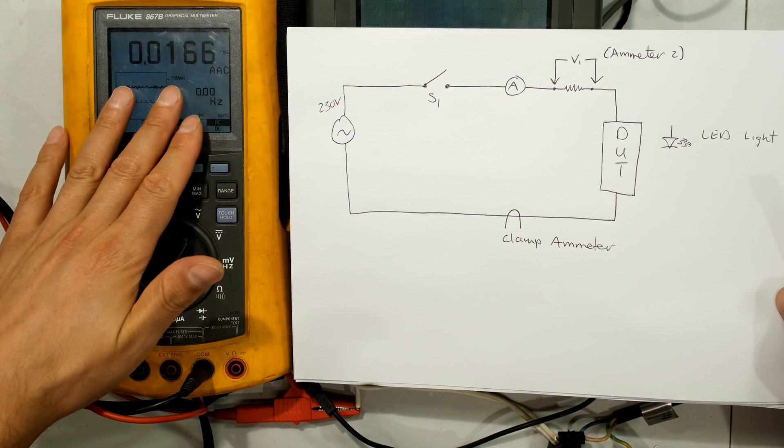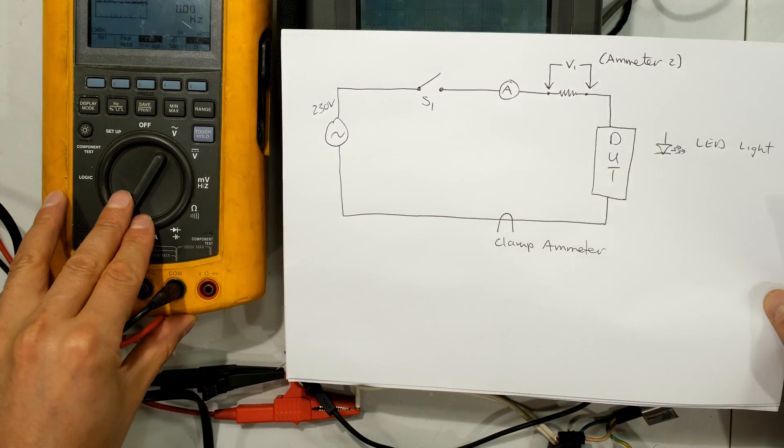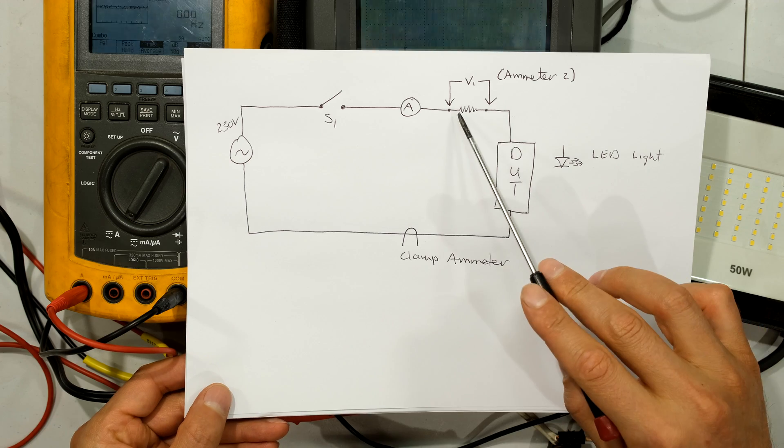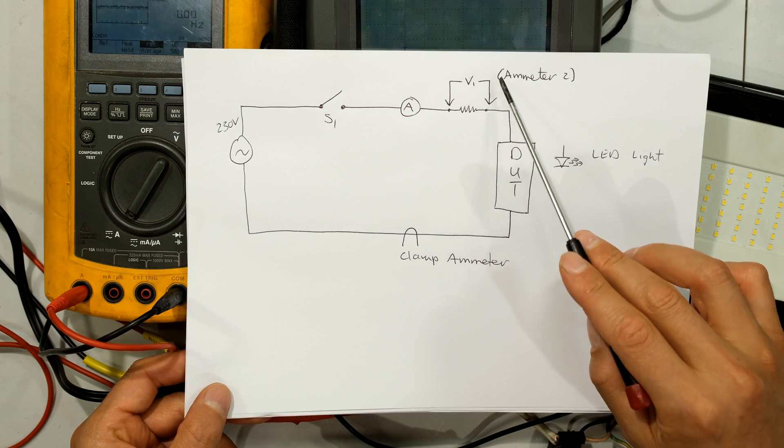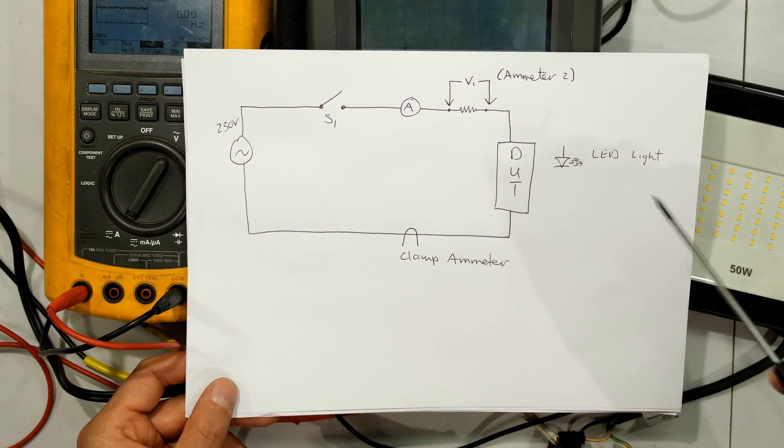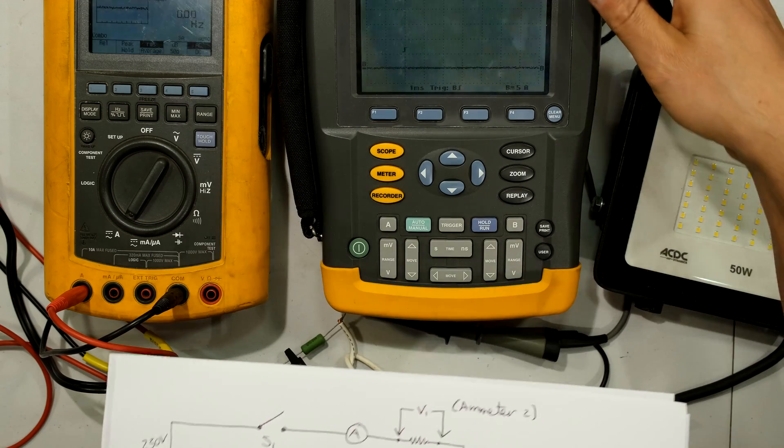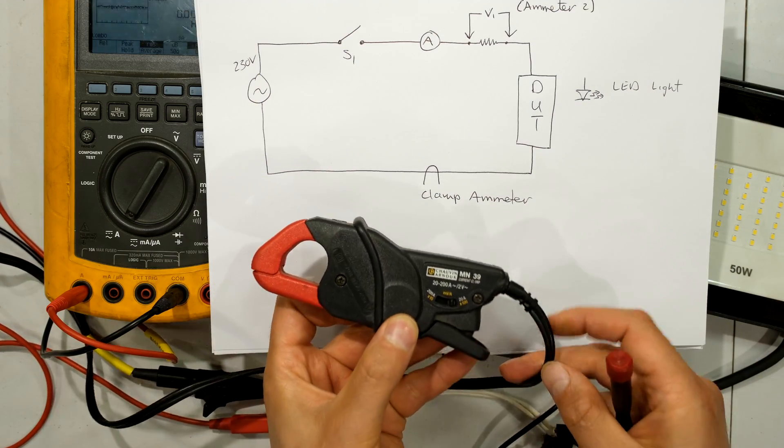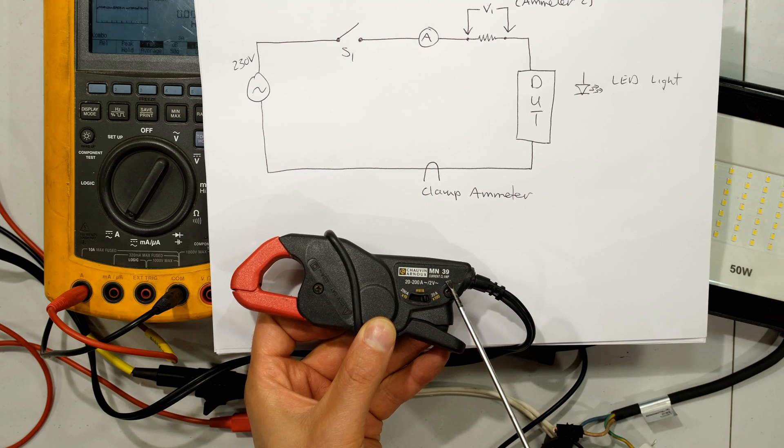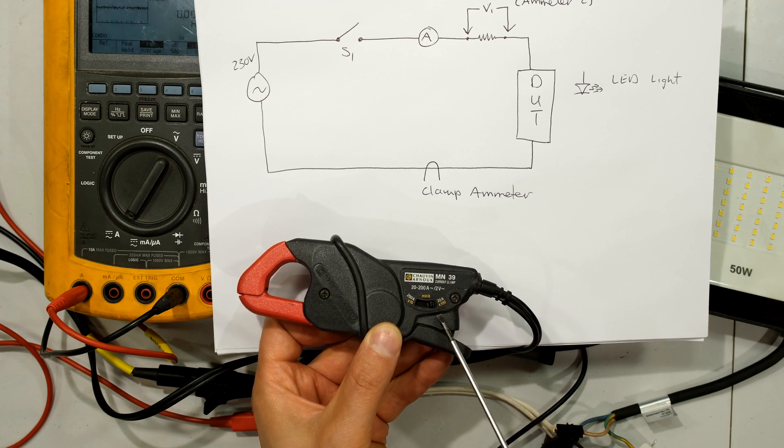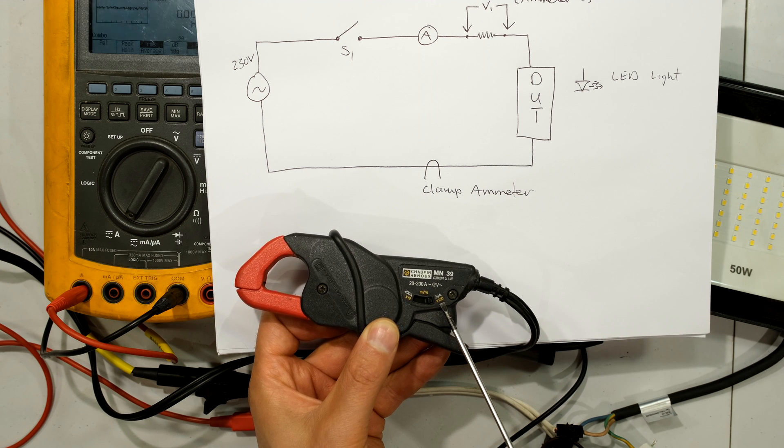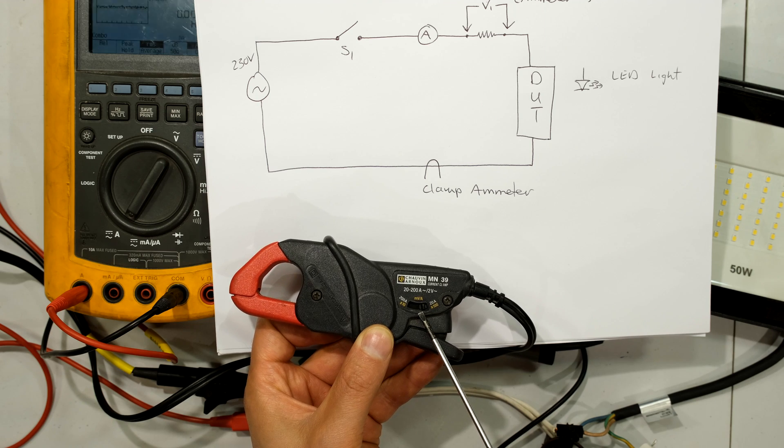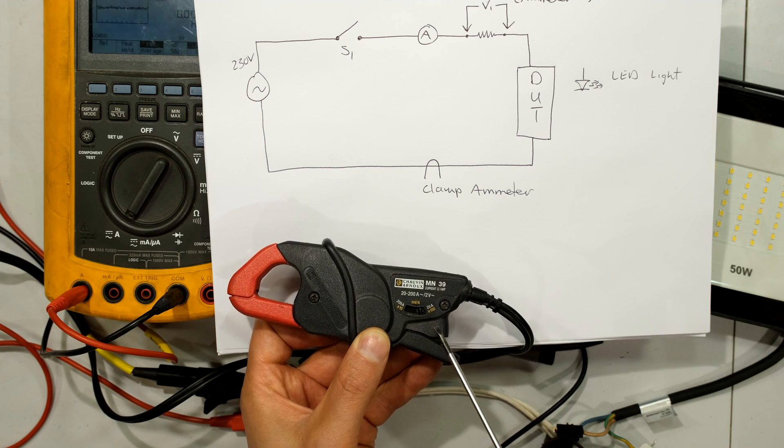I will be measuring the nominal current with the Fluke, and then I have this 1 ohm resistor which will create a volt drop which will be converted to a current measurement on channel B of the oscilloscope. Then I have this Chauvin Arnoux current clamp MN39 set to the 20 amp range on channel 1 of my scope meter.